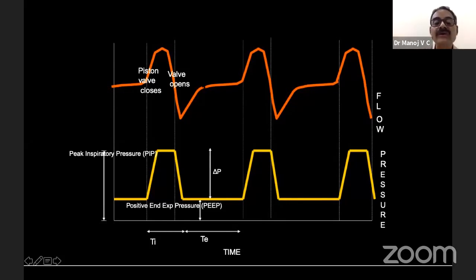Now this flow is going to generate a very, very important graph as far as a ventilator is concerned. If you call a biomedical technician into your unit and ask him to look at your ventilator, the first graph that he is going to look at is the pressure waveform, because this is what is going to tell you the integrity of the ventilator. Because you are using PCV, pressure control ventilation, the question is whether the pressure is delivered correctly. When the valve closes, the pressure starts building up in the lung. It reaches a point which you have set as a control on the machine. You cannot go beyond this. This is the peak inspiratory pressure. It will stay at that pressure until the valve opens.